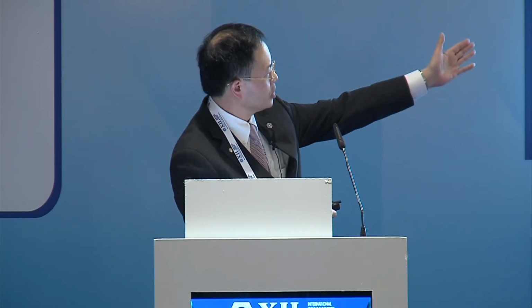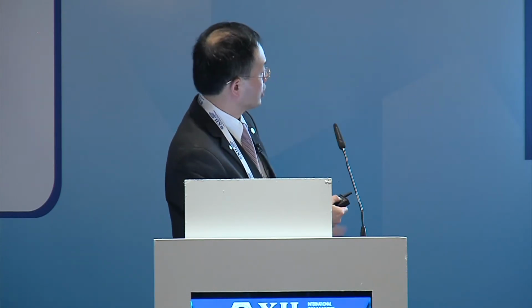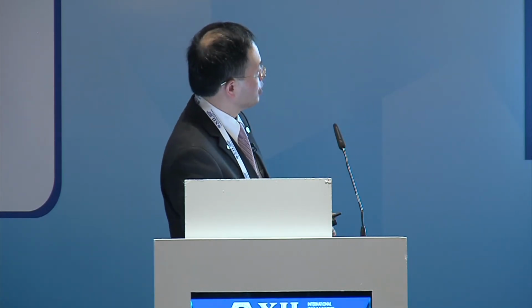Now let's talk about the room pressure control. Three scenarios. If you want to design a room in positive pressure, typically you want to supply more air than return and exhaust combined to achieve a positive room pressure. So in this case, the offset supplies more than departing air. Entering is more than departing air. Departing air is typically return and exhaust. To achieve neutral, virtually the incoming and departing air are at a similar or equivalent quantity. Negative pressure, you want to make sure the departing air is more than the incoming air.